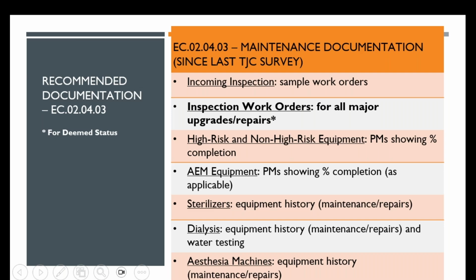All right, some documentation. Have a sample incoming inspection work order prior to initial use. If you're a deemed hospital, have samples of acceptance testing. So this also includes major upgrades or repairs, that you have that acceptance testing as well. And make sure any work orders you provide have the appropriate information. So if you're going to specifically do a Joint Commission binder and you're going to use a work order, make sure you're using a good one that actually lists the date, the measurements, the values, any test equipment that's used or whatever's called out in that specific PM if it is completed in-house.